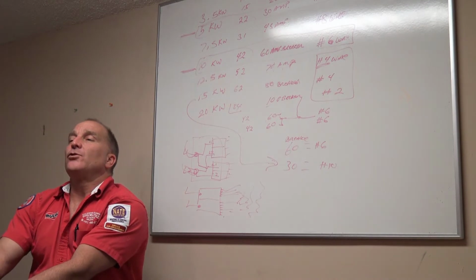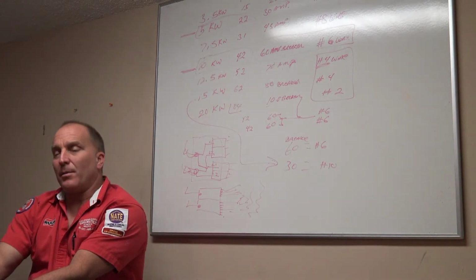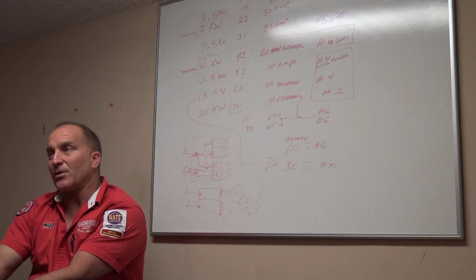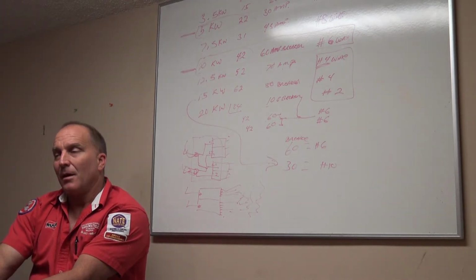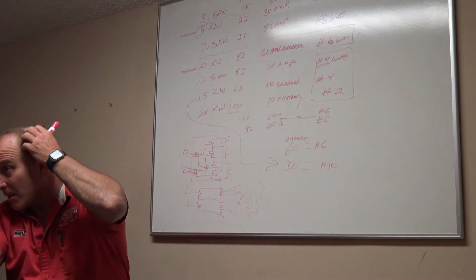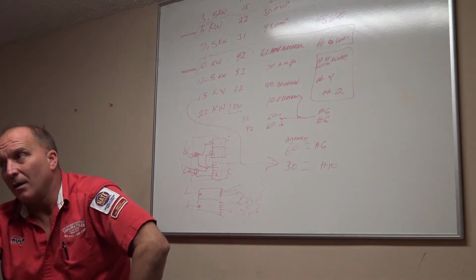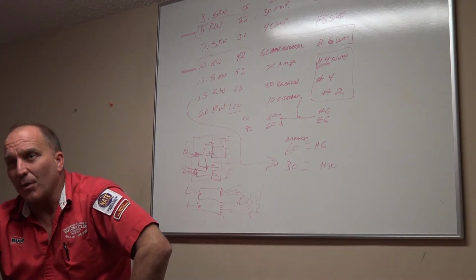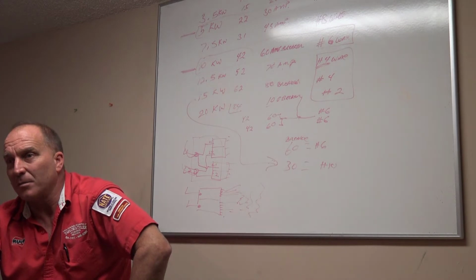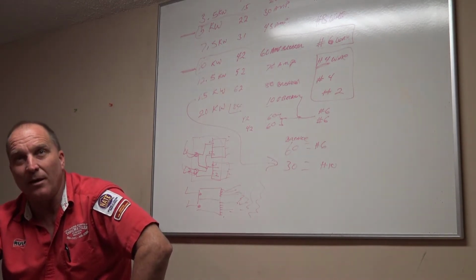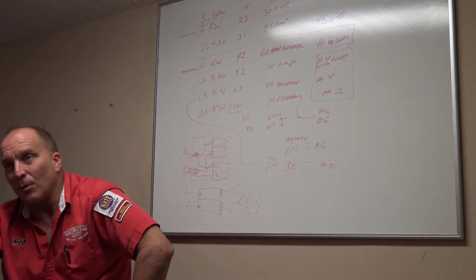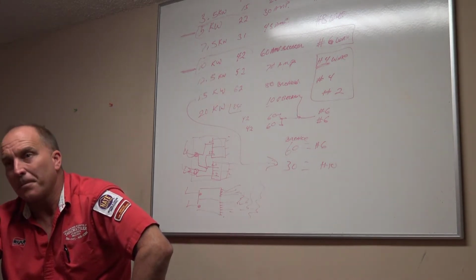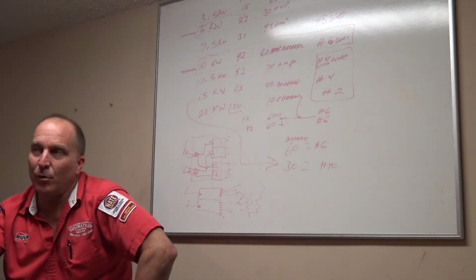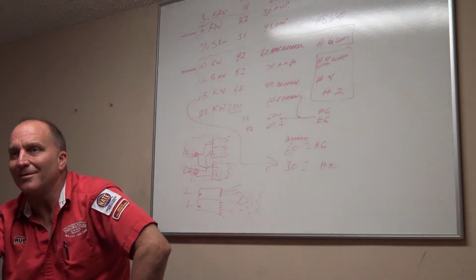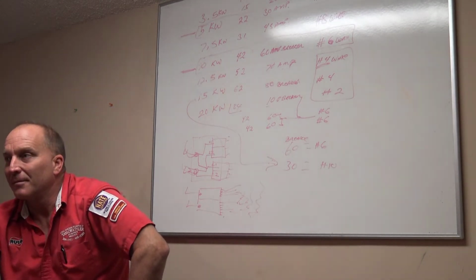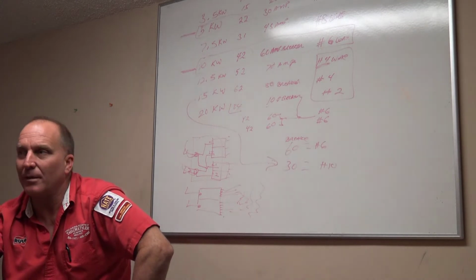Not only am I going to turn the air conditioner on, but I'm actually going to go outside to make sure the compressor and the fan motor came on outside. If I'm inside a vertical closet or something, I will grab the liquid line and suction line, and when I turn it on, you can hear the compressor come on 99% of the time, right? When it comes on, you're listening to it, compressor came on, okay, and then you can feel the flow of the refrigerant through your suction line or liquid line, and I go, okay, condenser's running. Because what if you blew the drain line and you pushed up the float switch and you didn't realize it? Or when you put the float switch back in, it cocked a little bit and it shut off.